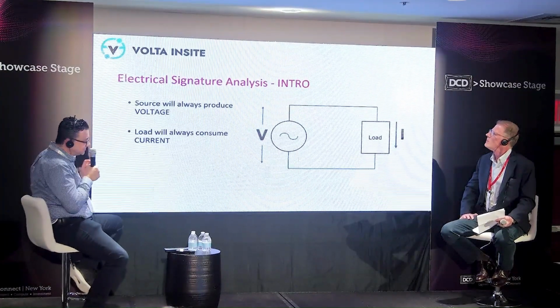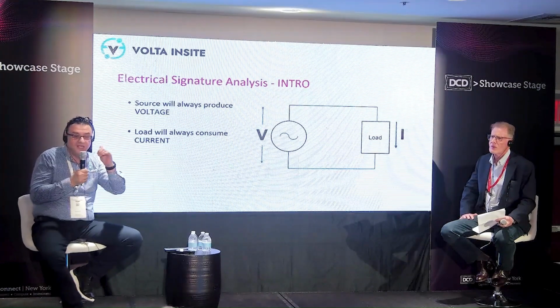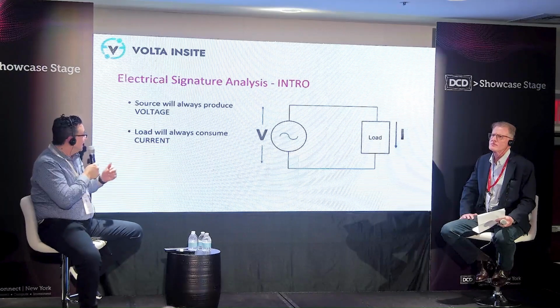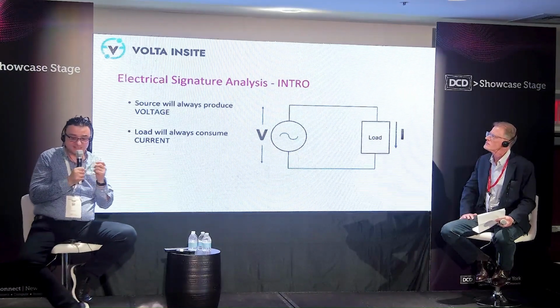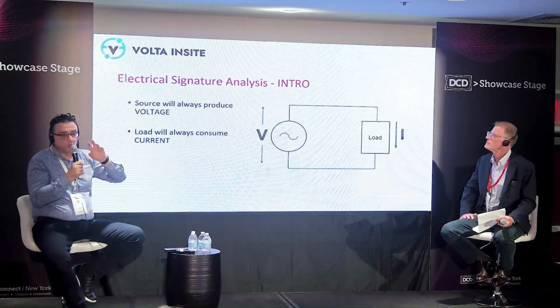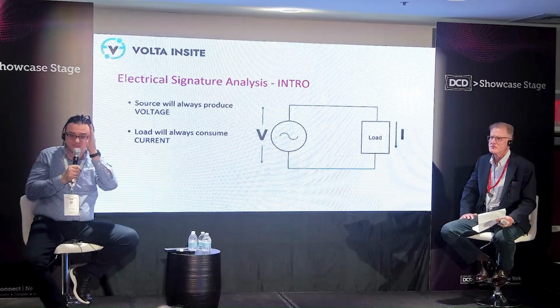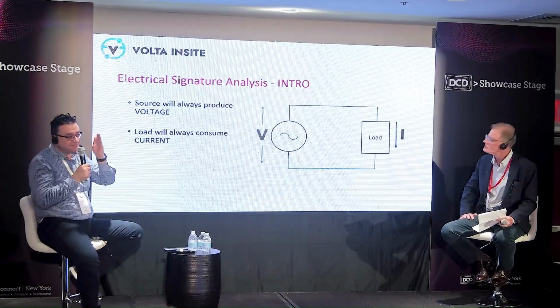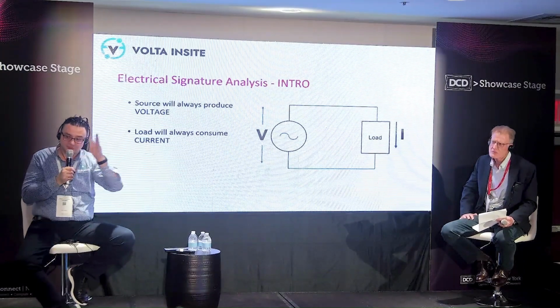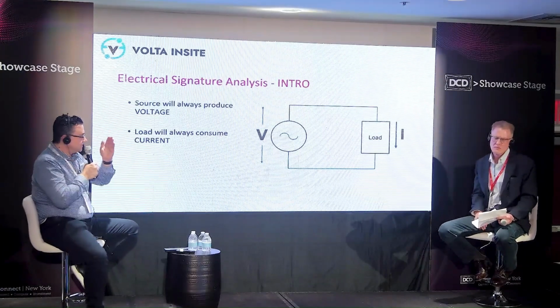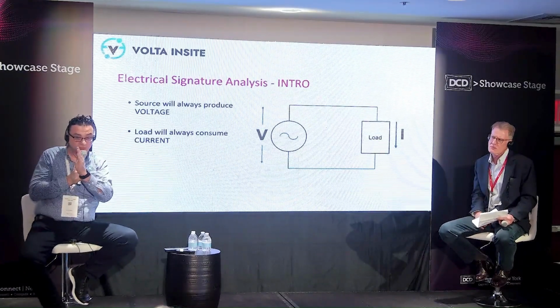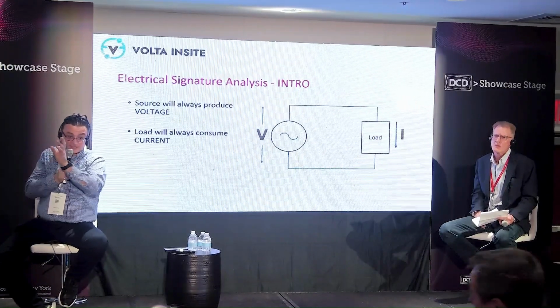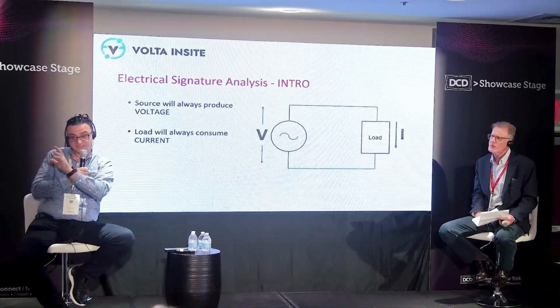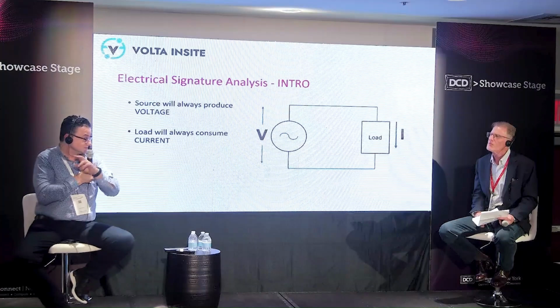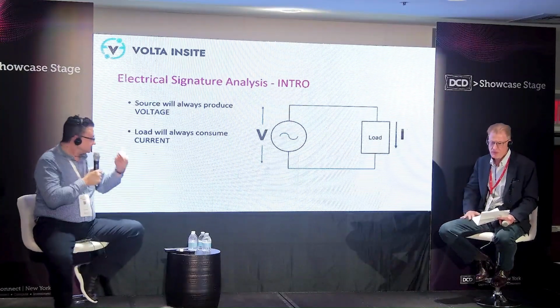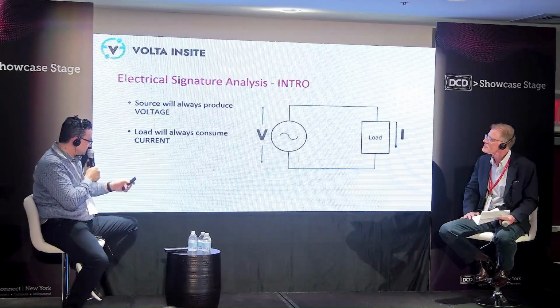Now, if we're always doing continuous waveform capture, we can go one step further into what's called electrical signature analysis. The basic premise is that anything to do with voltage, measured at one particular point, will be happening because of your power source. Anything you see on the current side will be a consequence mostly of the combination of voltage and your load. So if your voltage is stable and you see something happening in your current, you know the issue is on the load side.